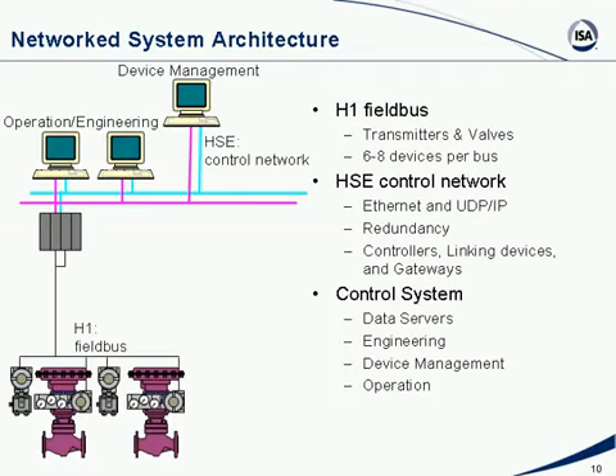Because Fieldbus runs at a moderate speed, the wire can be very long. It can be up to 1.9 kilometers or 1.2 miles, and this is of course very important for connecting field devices such as transmitters and valves, because they are very far away from the control room. You should always keep in mind that speed and distance always go hand in hand. So protocols that run faster can't run such a long distance. And the limited speed of Fieldbus also allows us to have spurs. That is, shorter wires that branch out from the main bus to the individual devices. We'll take a look at that in the next couple of slides.